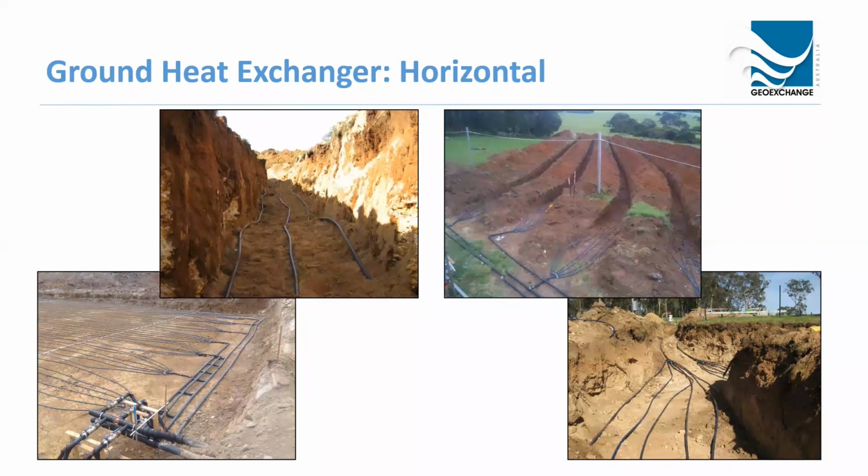So you get those 6 circuits in. Most of the systems we look at horizontally are a 6-pipe arrangement in that respect. Some can be 4, some can be 8. They're almost always 25mm. Every now and then there might be a 32mm pipe. Just a few of those variables that come into play on that design.